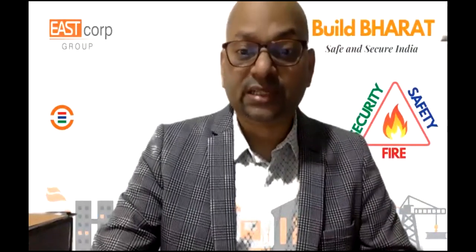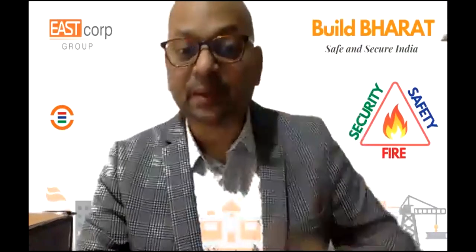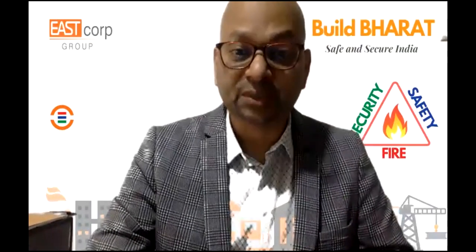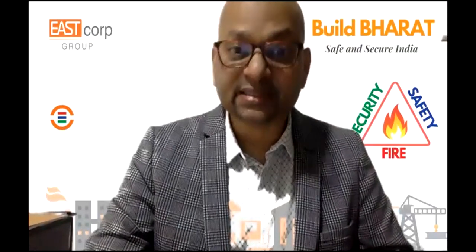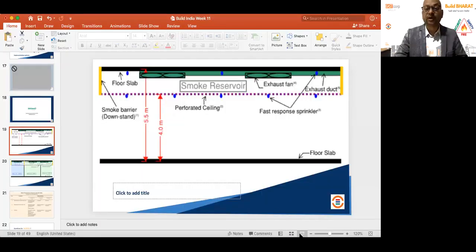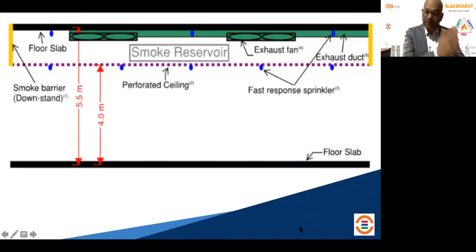So that's how we come up with passive protection compliances, so that it meets the requirement in both ways. Passive means you create a structure in such a way that it restricts fire and smoke for a certain period. The engineered way is using pressurization, dilution, and extra exhaust fan techniques, and you manage the smoke within less than 2 hours so that everything can happen safely.